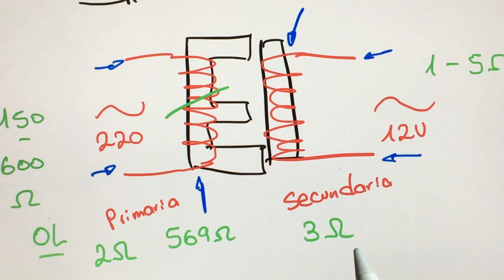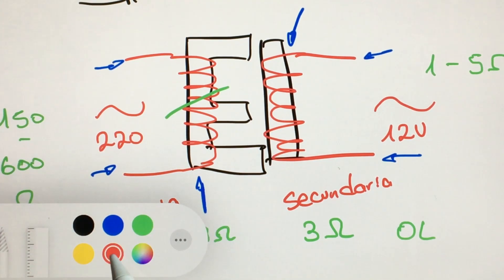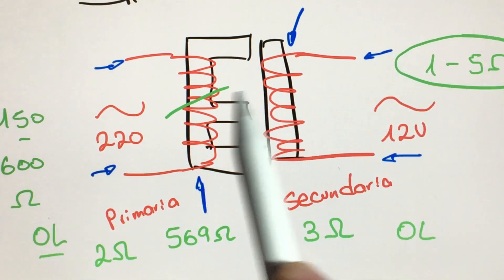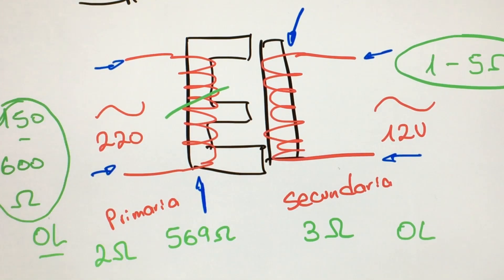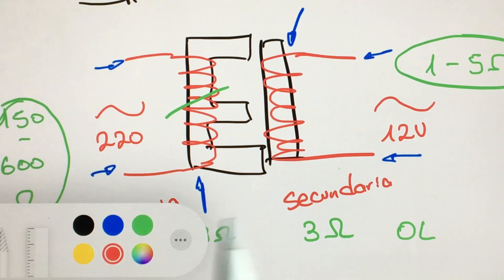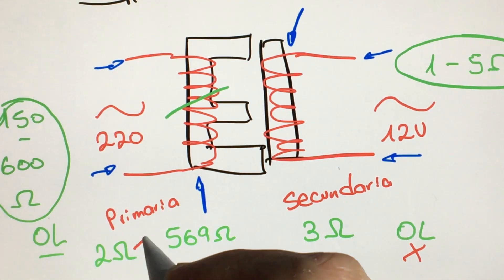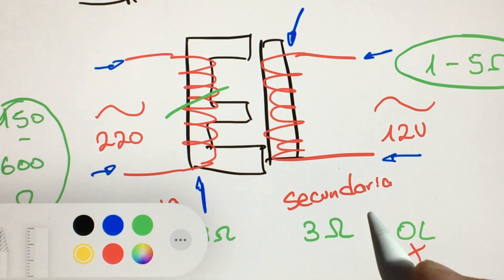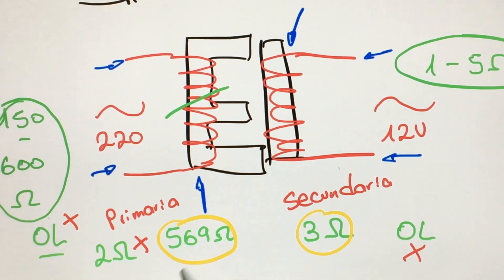And it would be the same on the secondary side. If I have a very high resistance, surely something has charred, and if I get O.L., obviously this coil has been cut. Taking into account the parameters, within all normal that a transformer brings, you can know if it is in good condition. In this case O.L. is bad, 2 ohms would be bad. And these are the values we just found in the sample transformer.